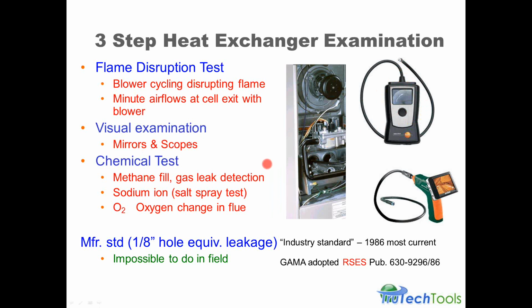And then there's the chemical test. The chemical test involves filling, it's also called a HET kit. It used to be manufactured actually by Sensit, but I'm not sure they manufacture anymore. But there would be a methane-filled heat exchanger chamber, blocking off the vent with some form of balloon or blockage, and then using a gas leak detector on the distribution air side to see if any of that methane is making it over. Tends to be a little bit more of a cumbersome test, and probably one of the reasons why it fell out of popularity. One of the sodium salt or sodium ion salt spray tests, where you look for a discoloration with a salt spray. But one of the more popular ones is the oxygen change, or the O2 test. And I think we have a slide on that next where we go over that in a little bit more detail.